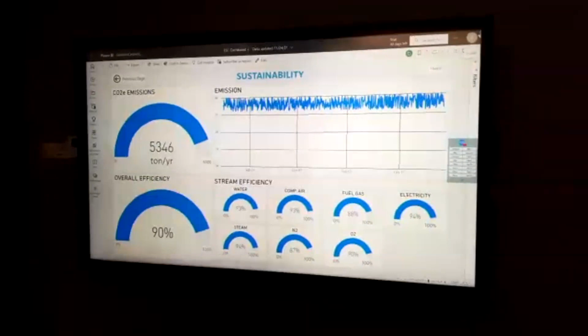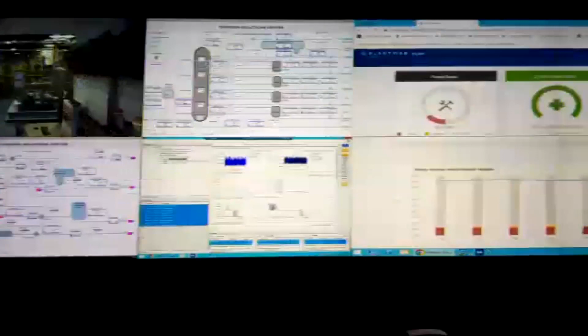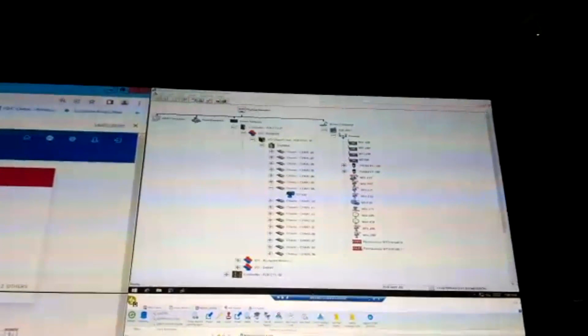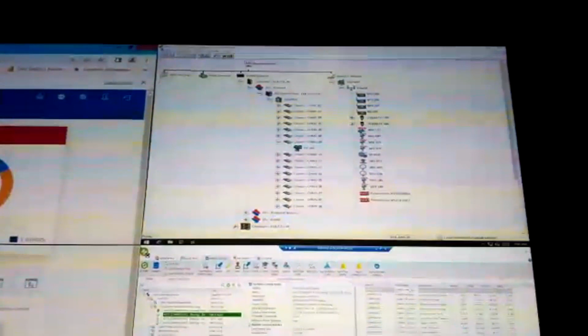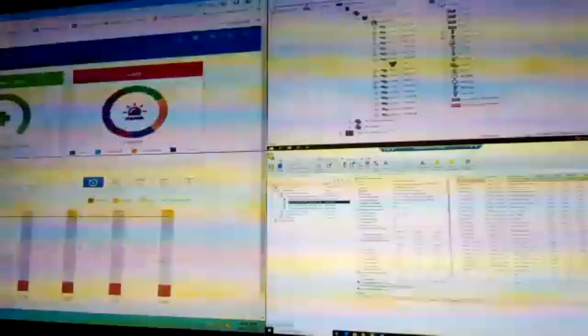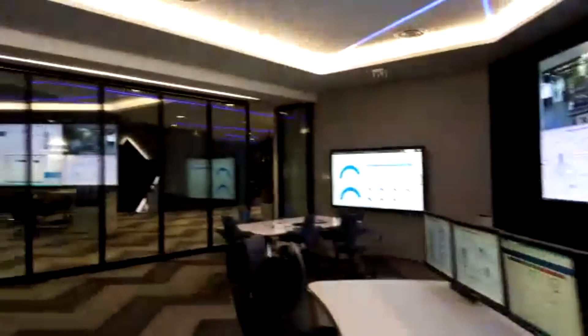All right, so in the solution center, here we got the video wall, and there's the analytics, and you can also get detailed vibration spectrum if you're dealing with vibration. But also what I wanted to highlight is intelligent device management, like the good old AMS device manager. So you have all of these wireless HART devices. You can also manage wireless HART devices from the same software that you use to manage your wired 4 to 20 milliamp devices and your field bus devices.